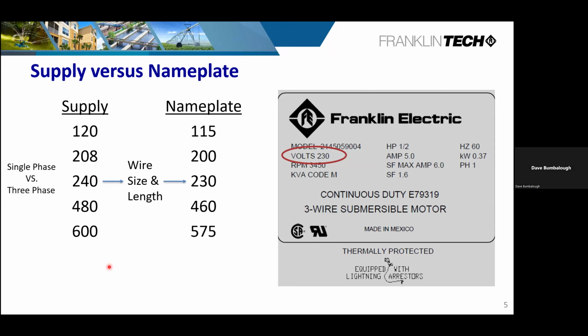And they're doing this because we're putting such a strain as consumers on that power grid, and they have no alternative but to crank it up to make sure the person at the very end has proper voltage. And so I don't know what steps are going to be taken going forward. Whether the manufacturers are going to have to put more forgiveness in their products, which is going to ultimately change the design big time. That's something that we can address. And what's going to happen is more than likely they're just going to take a horsepower of a higher rating and derate it, is what we're ending up going to do.